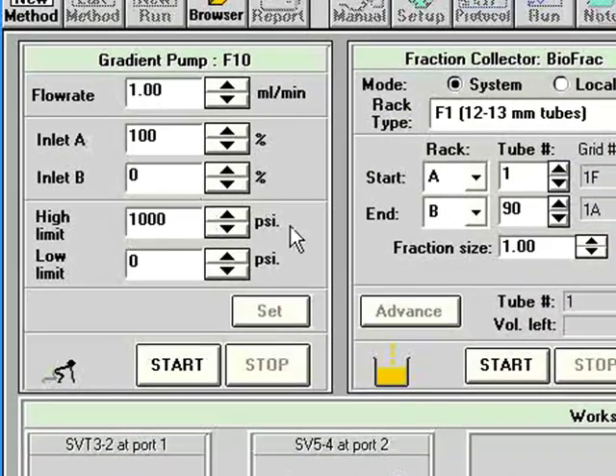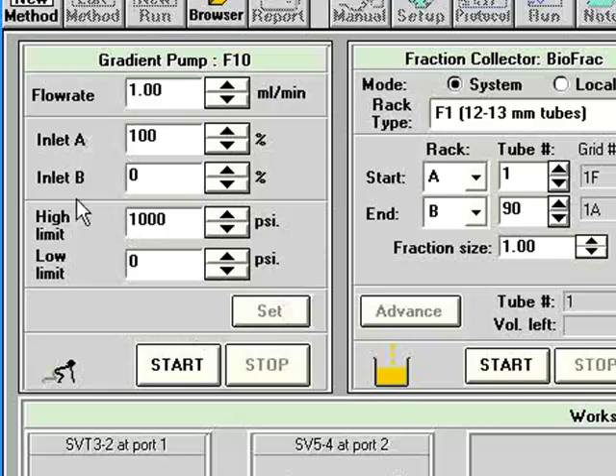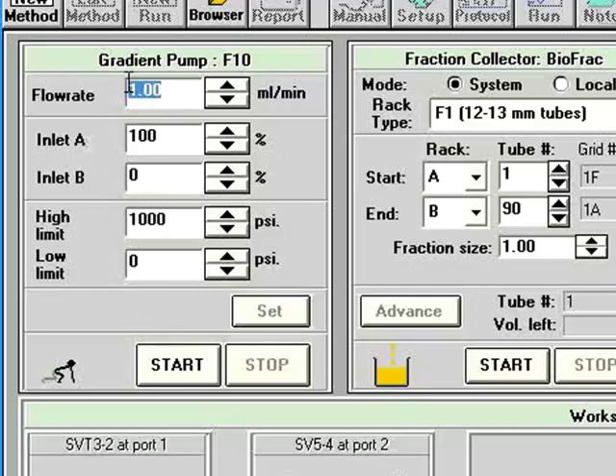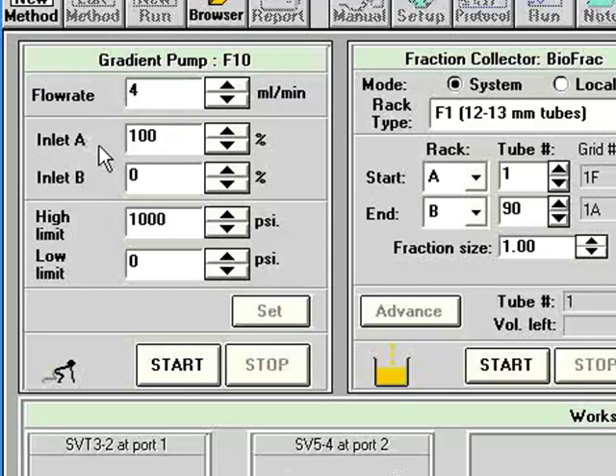When you open the system, basically what you would be using is these pump controls to initially purge the system and so on. Very straightforward to use. You can set the flow rate, let's say 4 mLs per minute. Hit enter. You can set the percent of A or B. Typically we recommend that A would be your low-salt buffer or your running buffer if you're using a gel filtration column, and B would be the elution buffer or the high-salt buffer if you're doing an exchange.